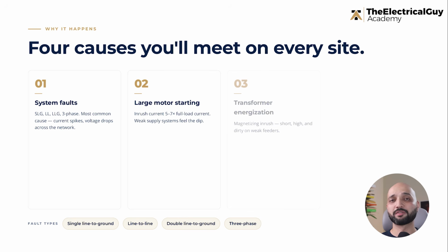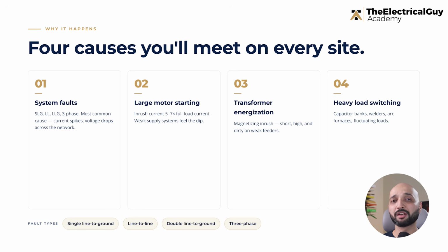Another cause is transformer energization. When a transformer is energized, it can draw magnetizing inrush current. This current can be very high for a short duration. In some cases, especially in a weak system, it can cause a voltage dip. Similarly, sudden switching of large loads, capacitor bank switching issues, short circuit in downstream equipment, welding loads, arc furnaces, and heavy fluctuating loads can also contribute to voltage variations.